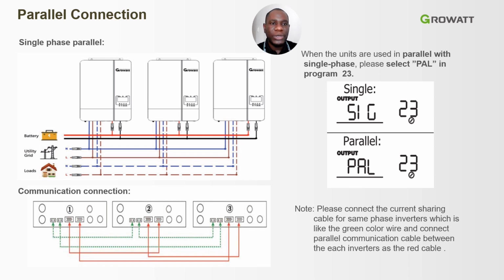So kindly note that when you are in parallel mode, these are the connections that you need to take note of, especially the communication connection, with the green cable representing the current sharing cable, and the red lines representing the communication cables. You configure or connect those cables according to the diagram shown on the left bottom part of that diagram. And in setting up your inverter in program 23, you need to instruct the inverter that you are operating in parallel mode. Then you select PAL. But this is single phase, so you still need to select SIG.